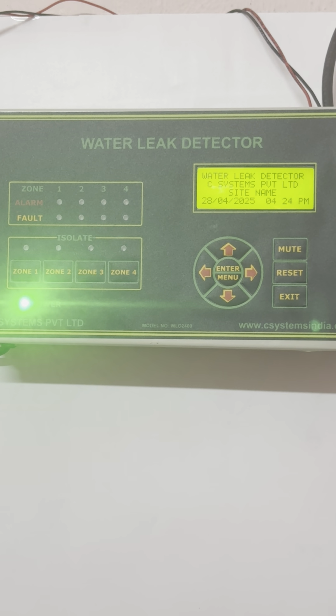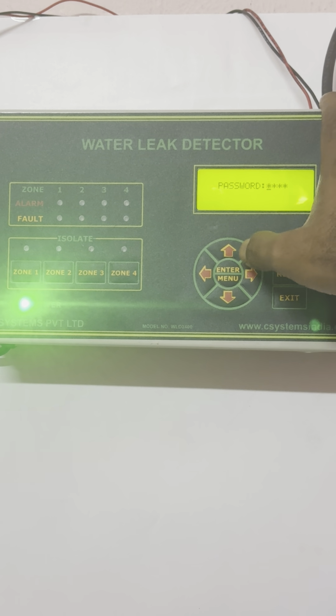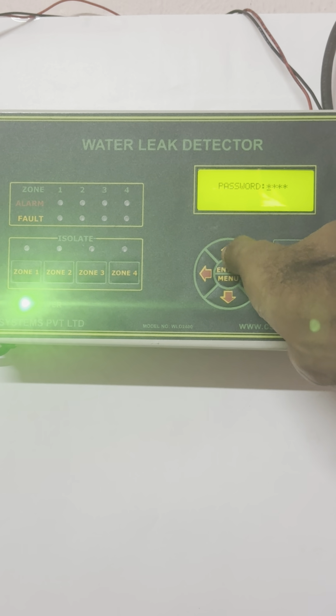After unboxing the panel and fixing it on the wall about 5 feet from the ground, when you power on the panel, you will see the normal display showing water leak detector in the first line, C Systems Pvt Ltd in the second line, and in the third line you will see configure zone. In factory condition, configure zone will be displayed, with date and time on the fourth line. To configure the zone, you have to log into the panel. Press enter. It will ask for a password. The password is written on the back side of the panel, on the sticker. It is 3929.